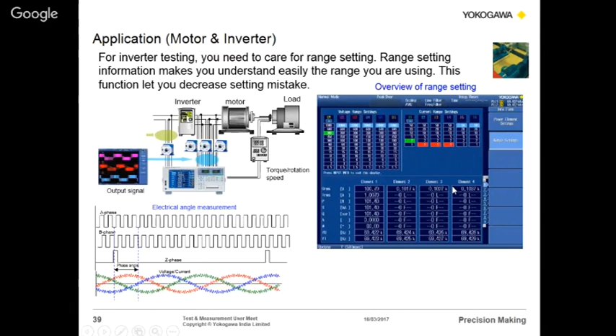So this is an overview of the complete range settings which we have done here. This is one of the applications for the motor and inverter. The advantage is high speed range changing. Sometimes, within a fraction of a second from when the motor starts, it goes to the highest peak because of the starting current, and then it stabilizes. That happens within 3 to 4 seconds, so the power analyzer should be able to respond to such fast changing signals.